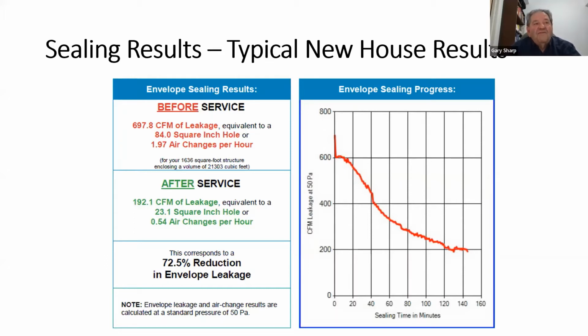If you look at the graph on the other side, what we're plotting on the graph is essentially the CFM of leakage, so the amount of leakage. And then at the bottom of the graph is the sealing time. So you can see that we sealed on this house for about 2.5 hours. And you can see how the curve comes down fairly significantly in the beginning, and then it starts to plateau out. And this is basically the type of curve we see with all houses.